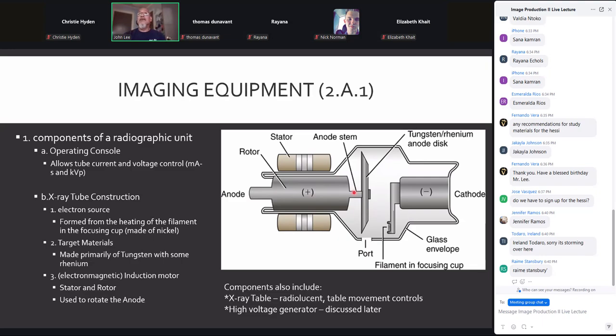Here, the stem, typically constructed of molybdenum, very, very lightweight, but extremely strong. Not that great of a heat conductor, but it does the job. Then, of course, we've got our rotor, which connects to the stem, and that has a magnetic bias to it and serves as the moving portion of our induction motor, made up of the rotor and the stator.